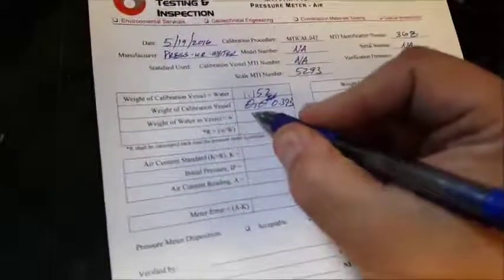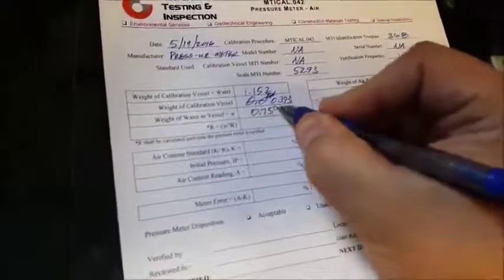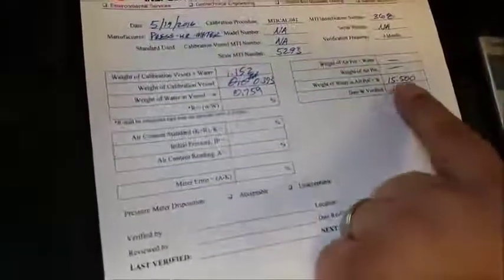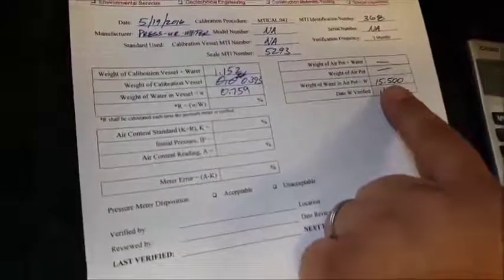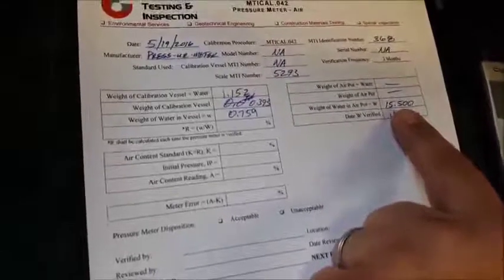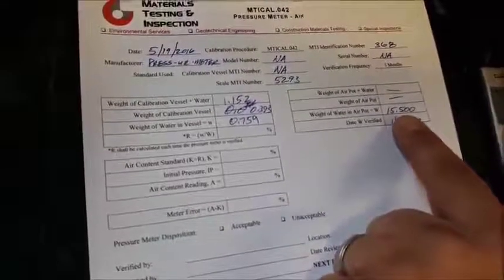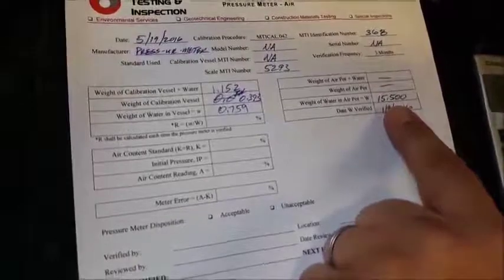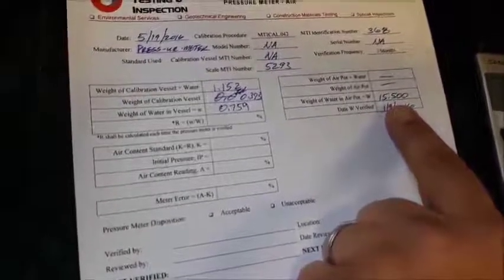1.152 pounds. Now we're going to calculate the weight of the water in the vessel by taking 1.152 and subtracting 0.393 to get 0.759. We're going to take that number and divide it by the weight of the water in the pot, 15.5, and multiply that by 100, and we get 4.9%.